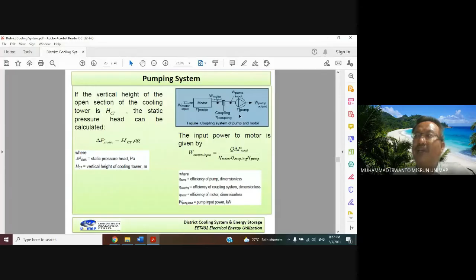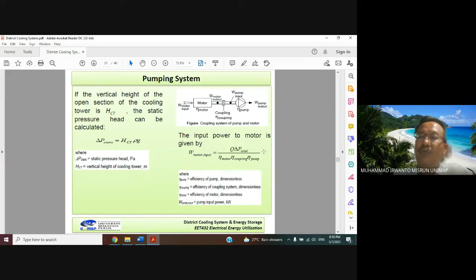When this occurs, the motor needs power. Here we give the symbol W motor input. The motor has efficiency, the coupling has efficiency, and the pump has efficiency. So the motor input is given by Q delta P total over efficiency motor multiplied by efficiency coupling multiplied by efficiency pump. Q here is the water flow rate, in the unit meter cubic per second.